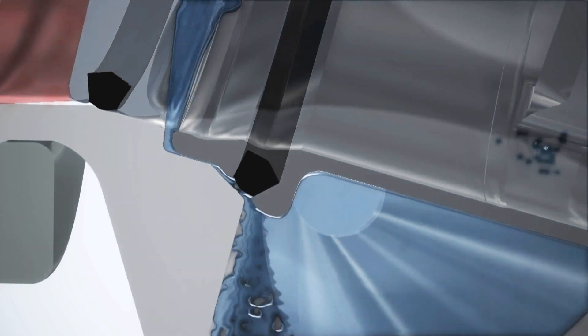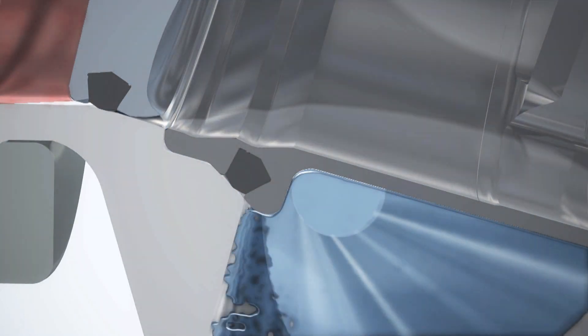The valve has two independent plug seals. The space between them forms a leakage chamber, which is open to the atmosphere. The CIP flow pattern between the plugs creates a vacuum at the opposite seal, a phenomenon which is known as the Venturi effect.